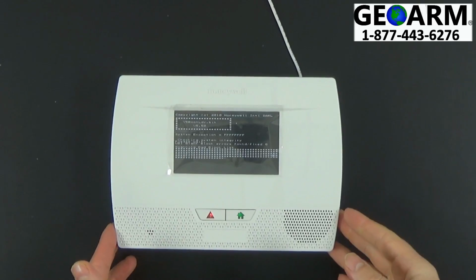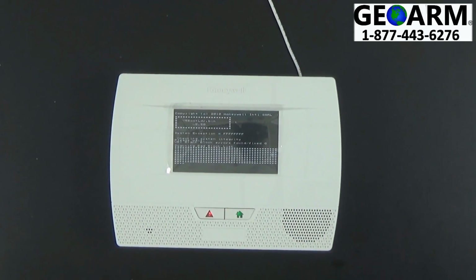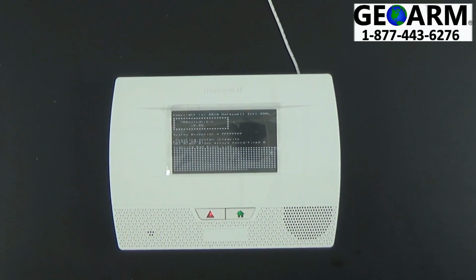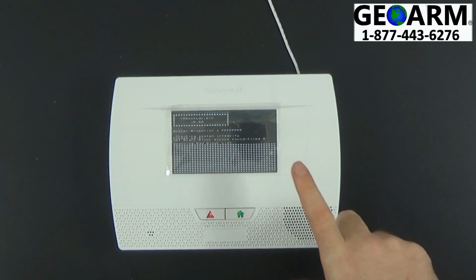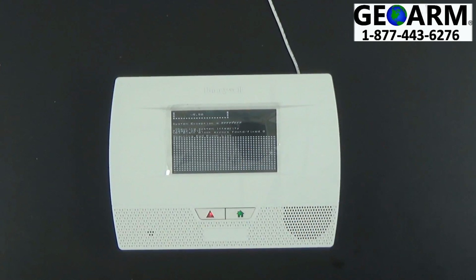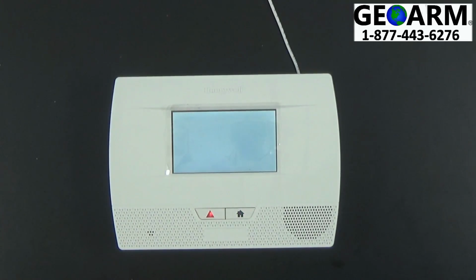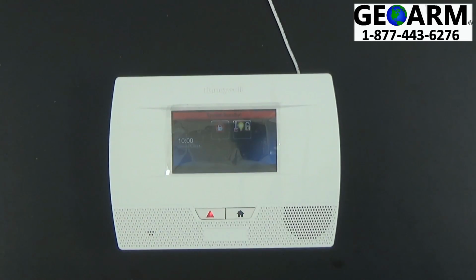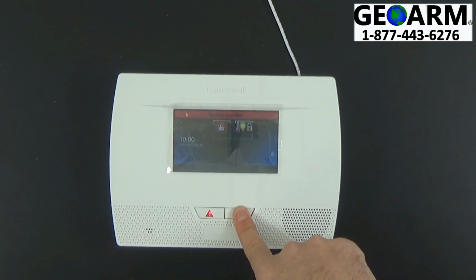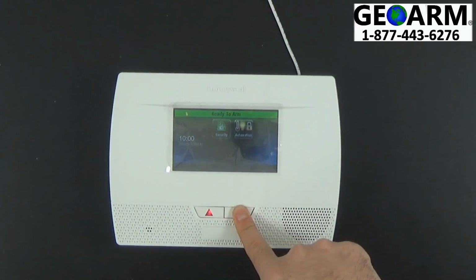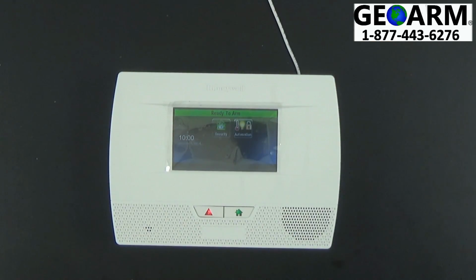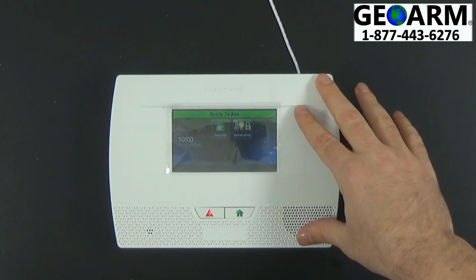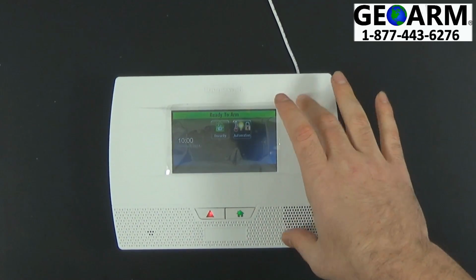As you can see, the panel is going through its booting process. Once it finishes, it'll take us to the home screen, which will be frozen for a few moments—I'll show you how to expedite that. Once you reach the system standby screen, hold down the home button for a few seconds to speed up that process. And that's how you hardwire the transformer into the L5210 panel without the LT cable.